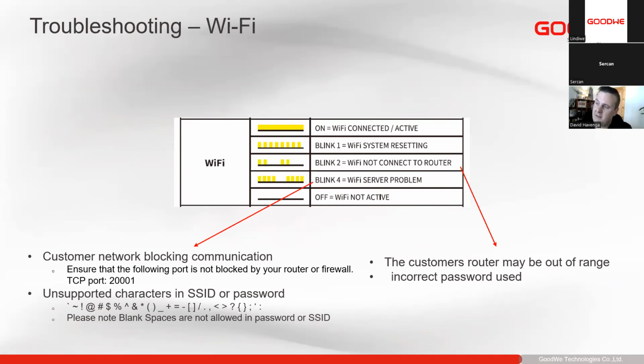Another condition could also be that sometimes the Wi-Fi module might try to reconnect and reconnect and reconnect, and after a certain time of trying, it's unable to reconnect, and then it will just sit in a stale, not connected scenario. What I suggest for any inverter that does this is to call our support team to update the firmware of the inverter. You can restart the Wi-Fi connection or restart the inverter. The connection should re-establish, or just press that reset button for a short time. It will restart and reconnect. The inverter's firmware now has the ability to automatically restart that Wi-Fi module. So should you have any problems, it will automatically restart the Wi-Fi module. It is something that we can do now for all the inverters.